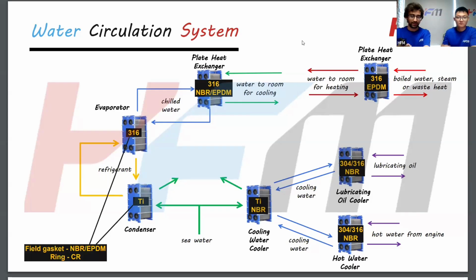Both the evaporator and the condenser are semi-welded, because the refrigerant isn't very suitable for gaskets either. So we have the refrigerant inside a welded plate, but we still need a gasket for the sea water in one case, or the chilled water in the other. In this ring, we are going to have a gasket, and the refrigerant is going to pass through here, so it's still interacting with the gasket somehow. There's a specific gasket we can use for this ring: chloroprene, or CR.